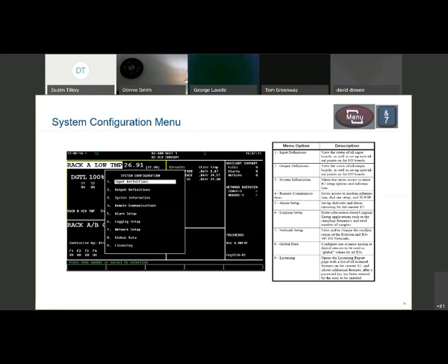From here, we can go in and define our inputs, the temperature sensors. We can name them and set them up specifically for what type of sensor we have, be it a temperature thermistor or a 5-volt, 200 PSI pressure transducer, through the input definitions. It's the same with the output definitions, only there you're specifying a relay state, whether it's open while active or closed while active, that type of thing.